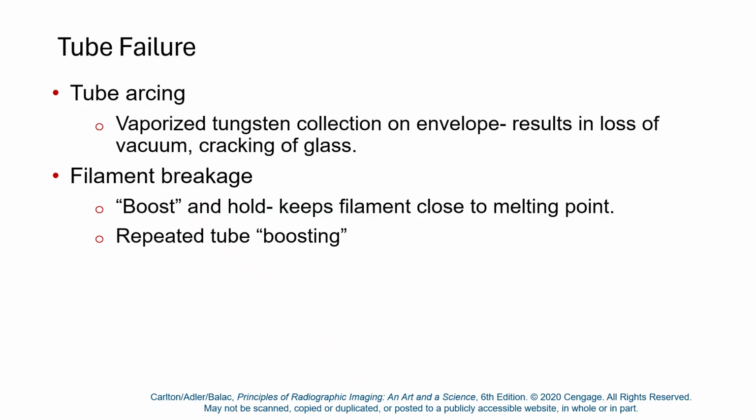When your filament runs hot with preparation, boosting, your filament does glow red hot, which is just before it turns to a liquid as far as metals are concerned. And the more you do that, the thinner the filament gets. The filament eventually thins out, and eventually it does basically evaporate away. You can evaporate your filament faster by abusing the preparation button and running excessive preparation.